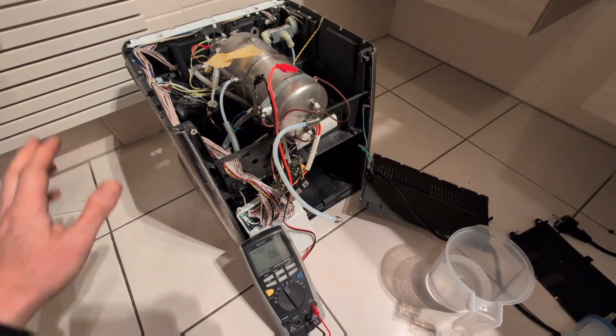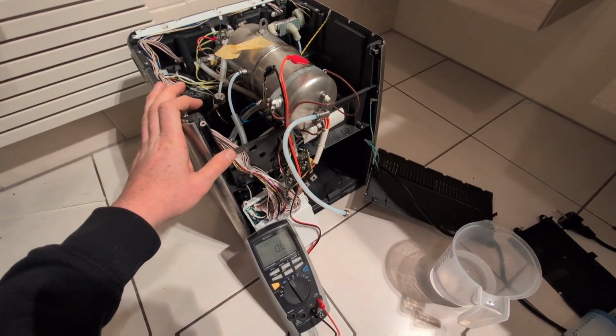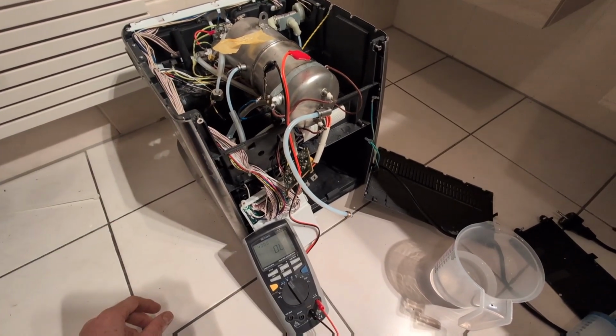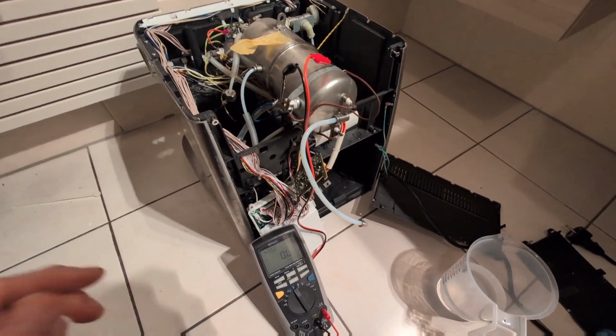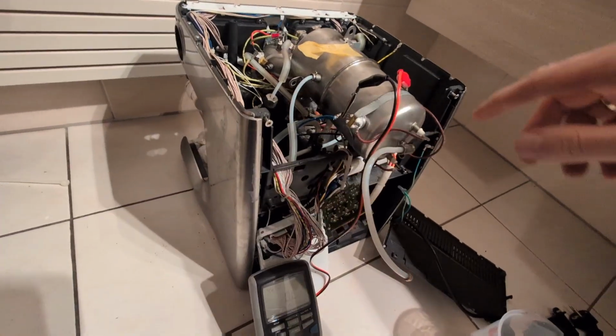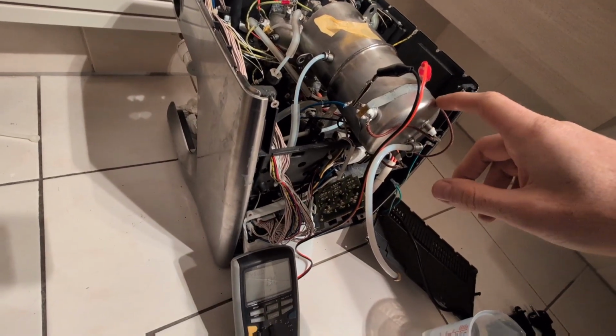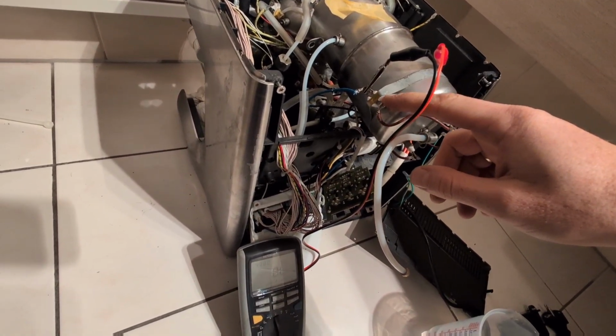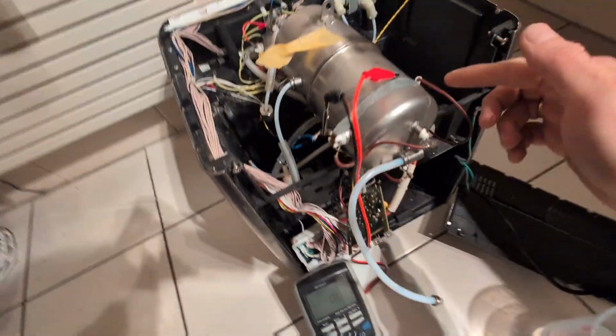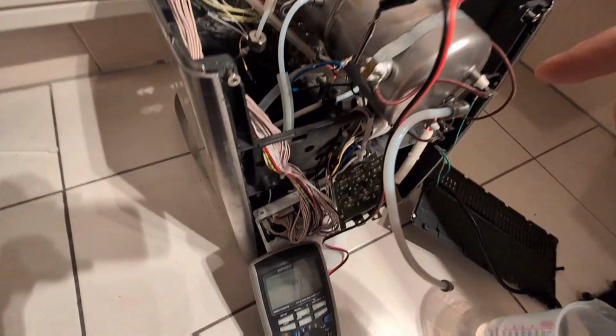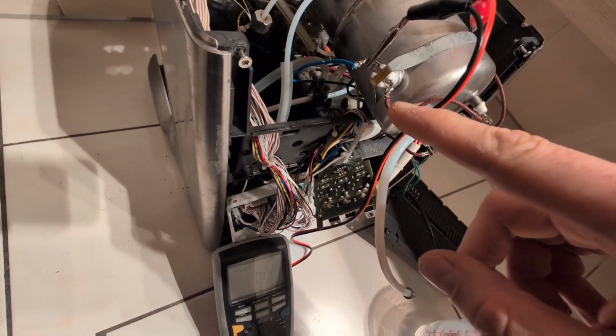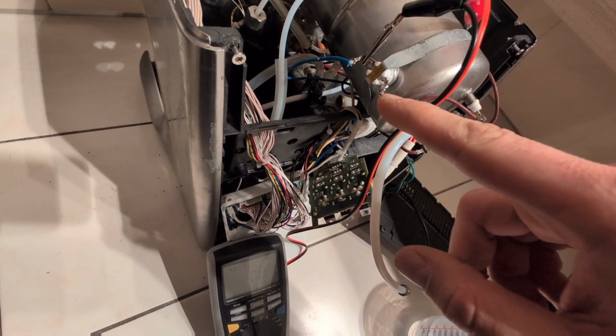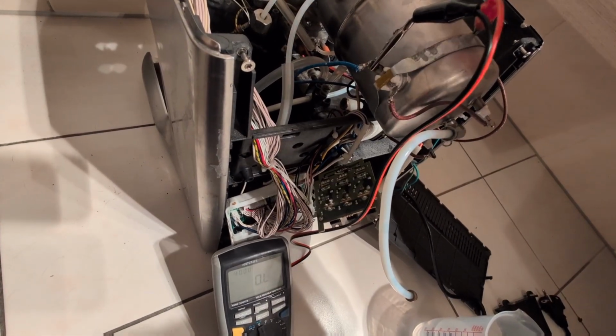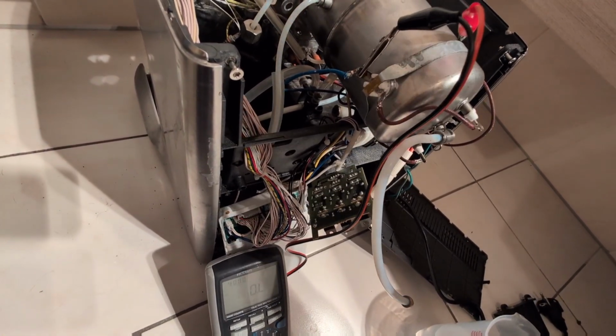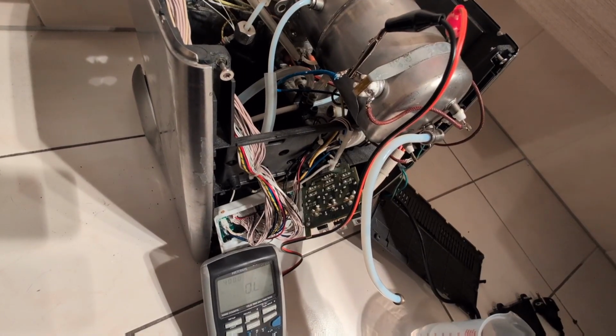Several days passed. I disassembled the machine, cleaned it a bit, and look what I wanted to show. Here on the boiler there is a thermostat and a thermal fuse. The thermostat is rated to 152 degrees Celsius.